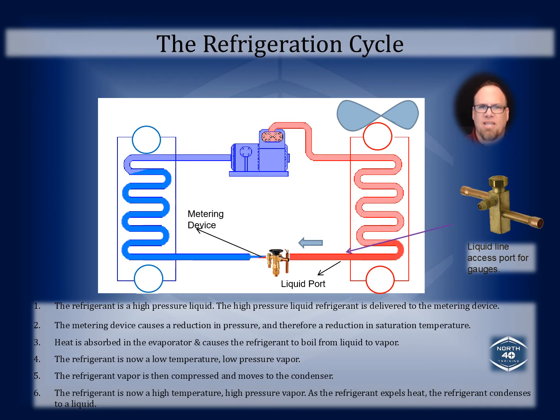If you can picture that same scenario happening as the refrigerant goes into the evaporator, the refrigerant goes from liquid form in the liquid line in a solid column of liquid to going through the metering device where it squeezes through a tiny opening, atomizes those refrigerant molecules so it spreads them apart. Now, why would we want to do that?